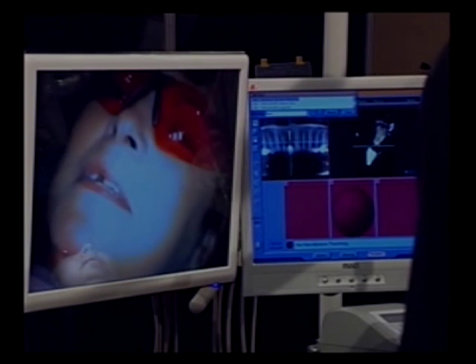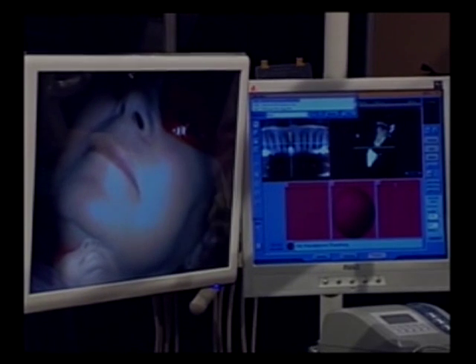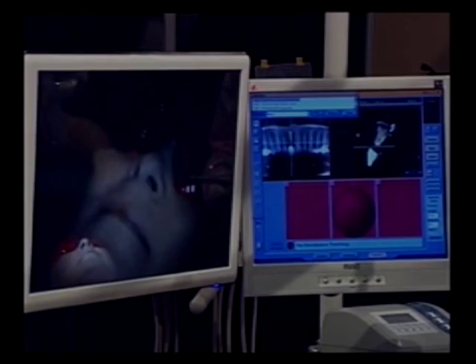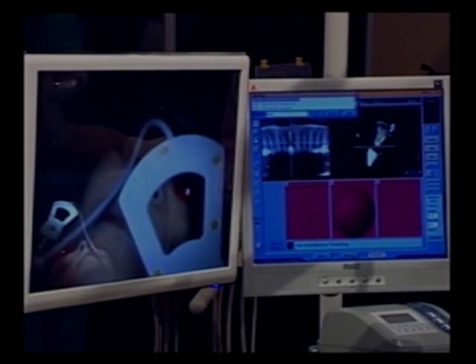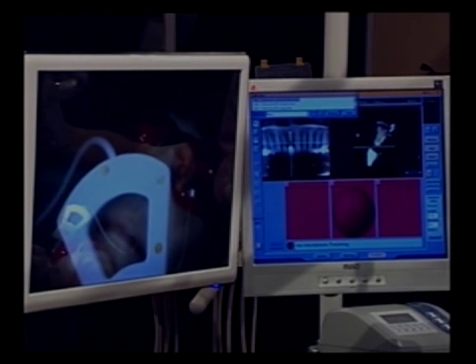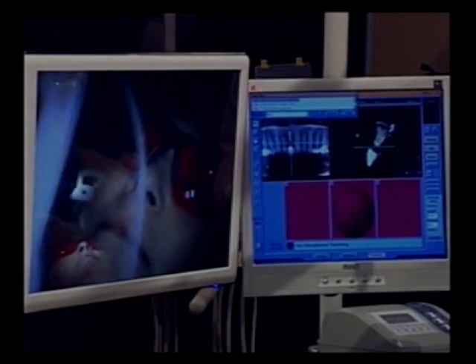What we'll do — this is the infrared receiver up on top. And if you'll hand over the patient tracker, Lana. These are infrared emitters. They send the signal to the camera; the camera or receiver will track Kathy's movement.